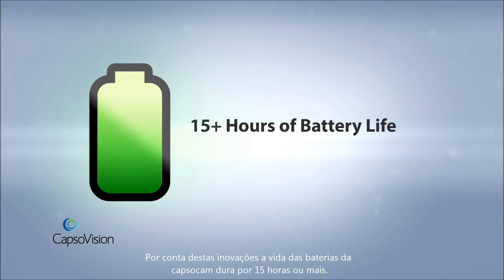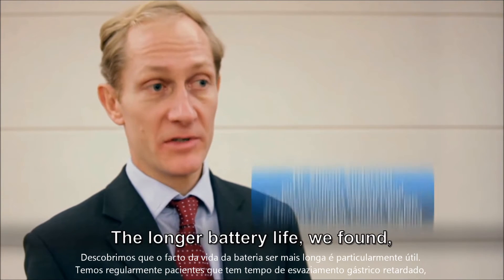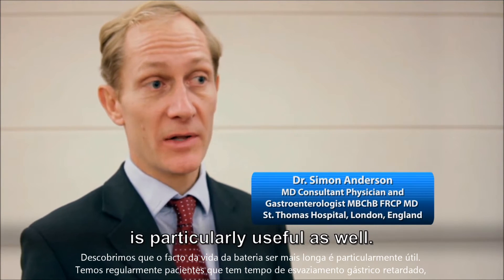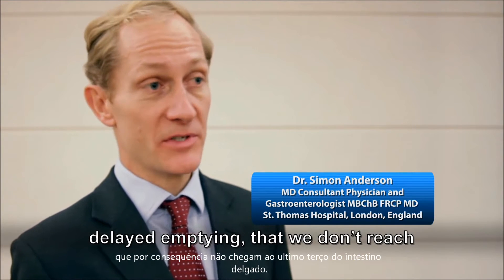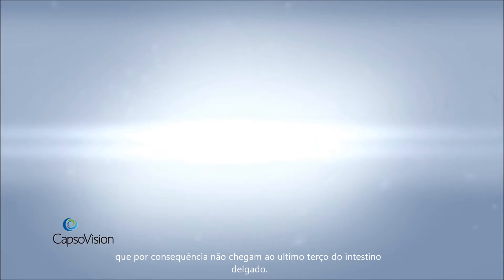Because of these innovations, the batteries in CapsoCam Plus last for an amazing 15 hours or more. The longer battery life is particularly useful for patients who have delayed gastric emptying, who don't always make it through the small bowel on other endoscopy systems.